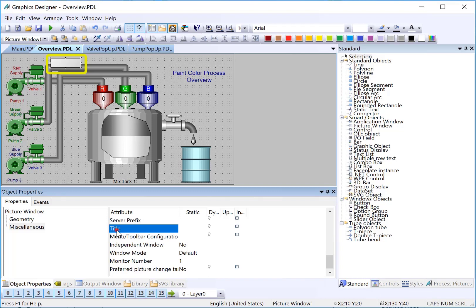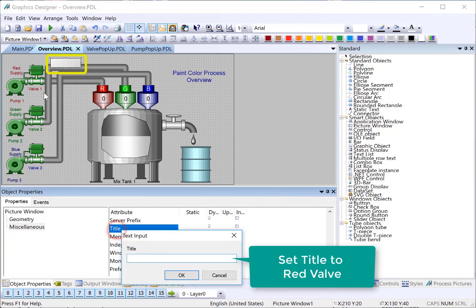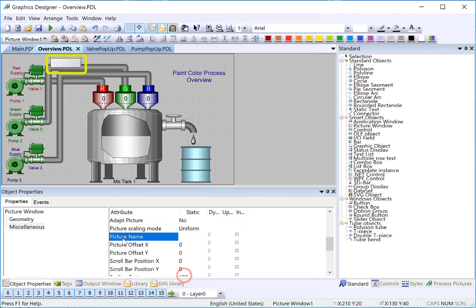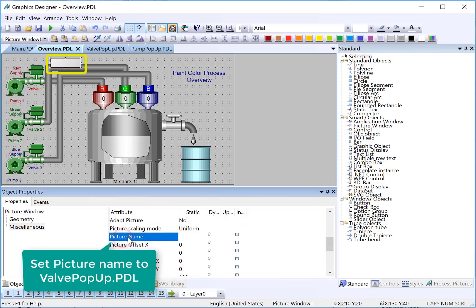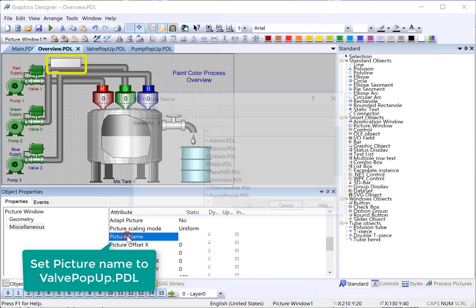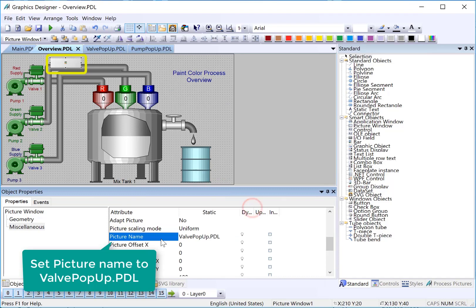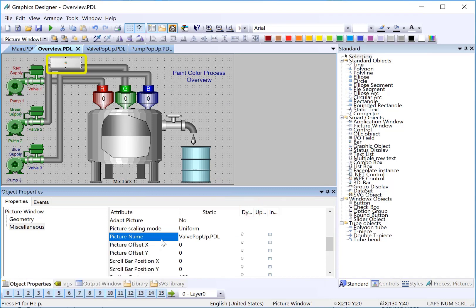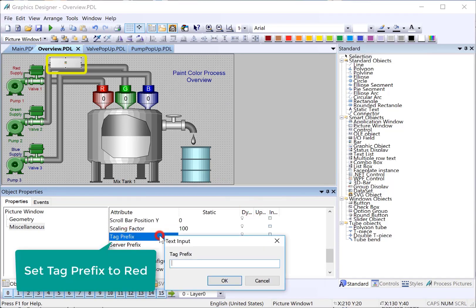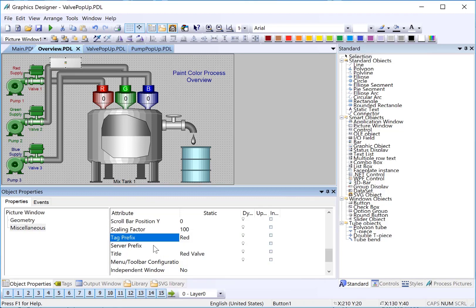And then for our title, this is going to be for our red valve. We'll just put red valve here. We're going to set our picture name. So I'll just double click here. That is going to be our valve pop-up. Since this is going to look at our red structure, we will go to the tag prefix property and just put red. And we have to make sure we spell it right and make the correct case. And the way this works is any tag request coming from the page shown in this picture window will have this appended to it.